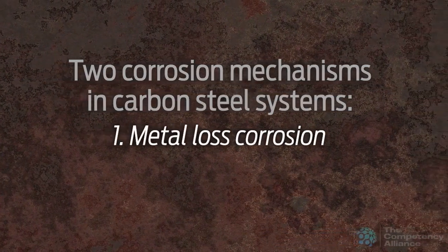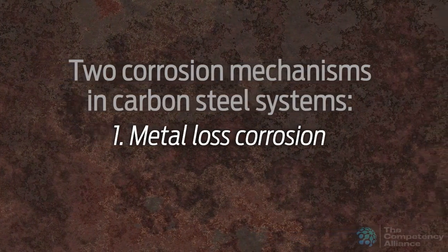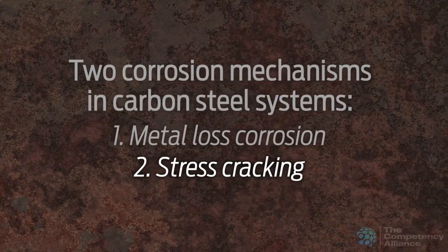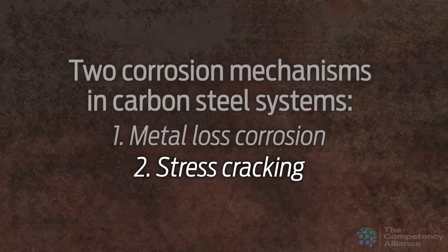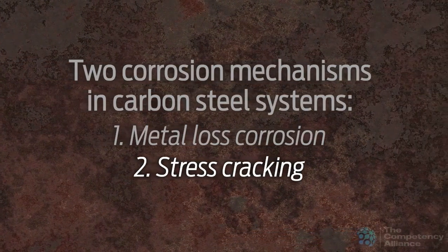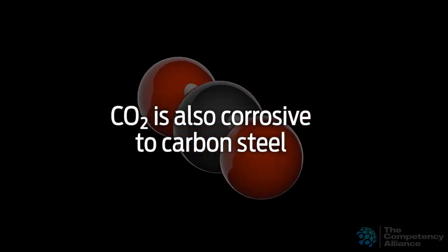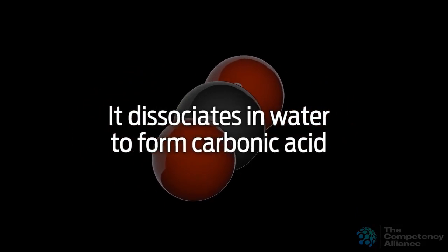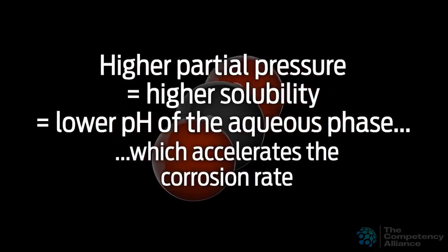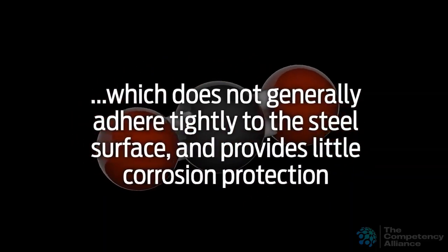Here are two corrosion mechanisms in carbon steel systems. The first is metal loss corrosion: H2S dissociates in water to form a weak acid, and the corrosion product is iron sulfide, which adheres tightly to the steel surface and often inhibits further corrosion. The second is stress cracking, which is generally more important — it is difficult to detect and can lead to sudden failures. Systems designated SOUR in NACE MR0175 or ISO 15156 are considered susceptible to stress cracking failure and require selection and use of certain steels and welding procedures. CO2 is also corrosive to carbon steel; it dissociates in water to form carbonic acid. The higher the partial pressure of CO2, the higher its solubility and the lower the pH of the aqueous phase, which accelerates the corrosion rate. The corrosion product is iron carbonate, which does not generally adhere tightly to the steel surface and provides little corrosion protection.